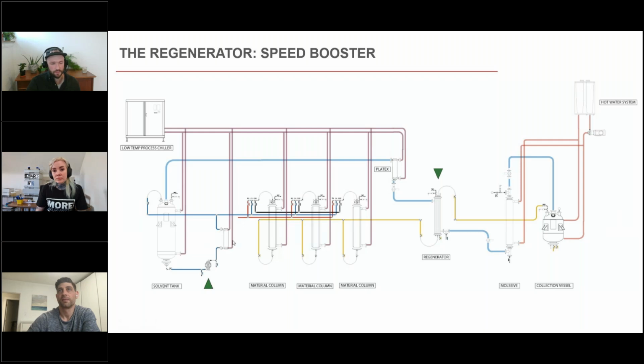While we're at it, we should talk about the other plate exchanger that we use, which is to cool your solvent on your way to extraction. So let's say you're condensing at 0 degrees Celsius or minus 10. Then as you pump it out of the tank to send it back through the loop, you go through another plate exchanger, which cools it down to your extraction temperature, minus 40. Again, the game here is just surface area and kilowatt capacity.